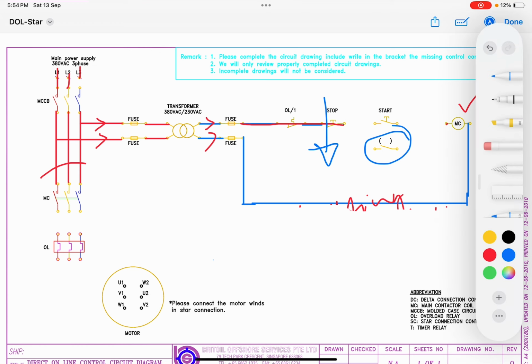So now this stop push button is also spring loaded. So even though you release the stop push button, right, what will happen? Again it is going to close, right? So if it is closing, what will happen? Again power supply will pass from the stop push button, it will go to the start push button, and then it is going to wait near this start push button. So now again we have to press this start button, then only is my motor going to start, otherwise it will remain in the stop position. So this is how the circuit is going to work.